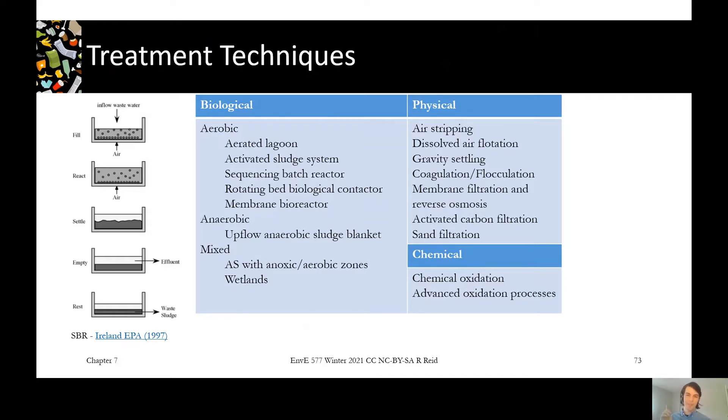So we've got things like air stripping to take out volatile things like ammonia and some of those dissolved gases, methane. Dissolved air flotation can help remove some grease and solids. Gravity settling, just like our first step primary clarifier in normal wastewater treatment process, we can get some of that high solids load out.